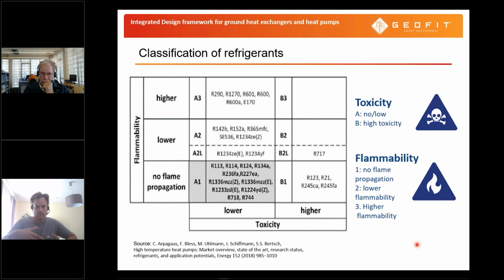So we have refrigerants which can be flammable and also toxic. These are groups which on the one hand have a low global warming potential, but on the other hand are flammable and toxic. And when taking into account heat pump systems with new refrigerants, we also have to deal with this classification. Using a flammable refrigerant, depending on the refrigerant charge you have in your system, you have to take measures, let's say, for instance, proper ventilation, so that no flammable gases form with indoor installation. So this also affects the cost for your heat pump systems, which is of course an important number.